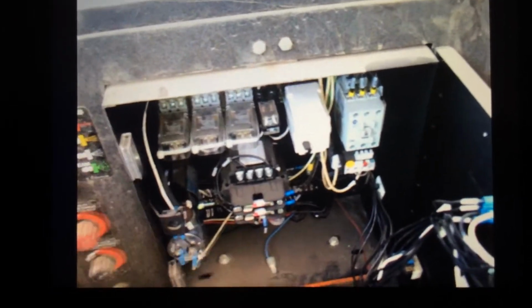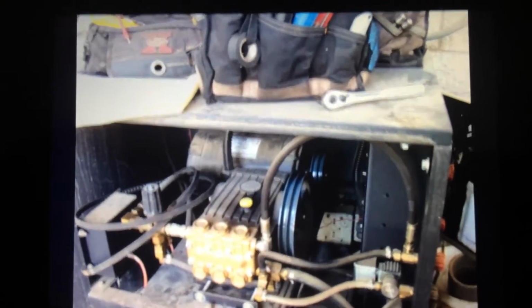Now we need to find out why the motor went bad. Very possibly it could be that this unit right here is actually built for 230 volt power. While we were checking our voltage at the top of the contactor, we found that they have 210 volt line voltage, which is only going to go down once it's under load. Typically under load we'll see a 210 volt line drop down to 208, 205. That means that this unit should have been a 208 volt motor, and it's a 230 volt motor trying to run on 208, causing premature failure. So we have to have a conversation with the customer now to see if they want to replace it with an OEM motor at 230 volt and take their chances, or if they want to convert the system over to 208, which is what it should have been to begin with.